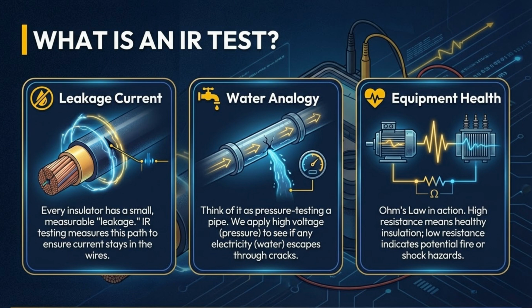What is an IR test? It measures the small, measurable leakage current in an insulator. Using a water analogy, it's like pressure testing a pipe for leaks. A high resistance reading indicates healthy equipment, while low resistance suggests potential hazards.